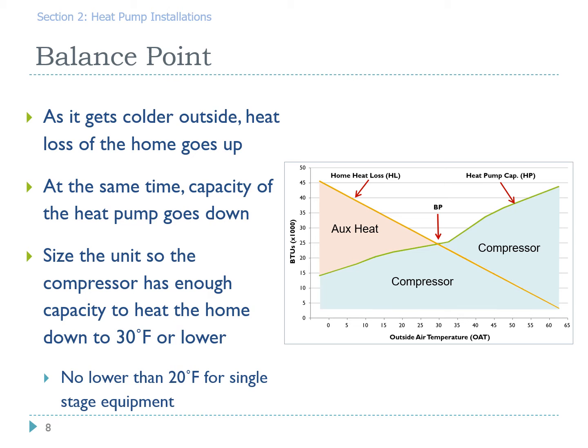Size the unit so the compressor has enough capacity to heat the home all the way down to 30 degrees. And then it can heat a little bit lower than that, but then we can add that strip heat in. So we want that balance point to be at 30 degrees. Now, little hint, for single speed pieces of equipment, getting lower than a 20-degree balance point might oversize and not be able to dehumidify in the summertime humid conditions.